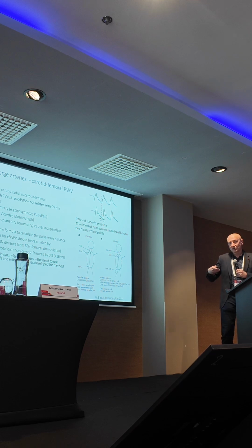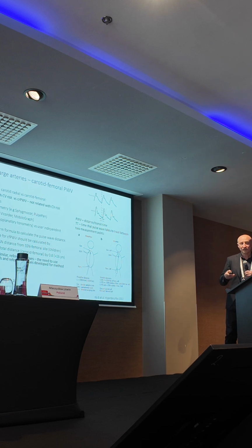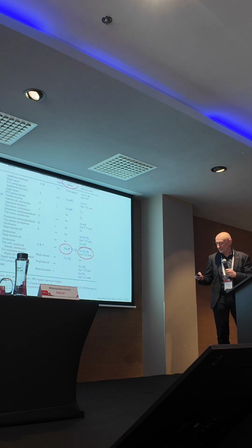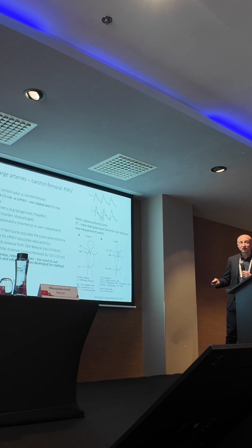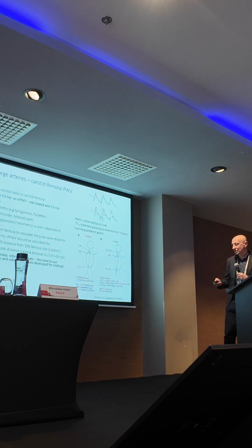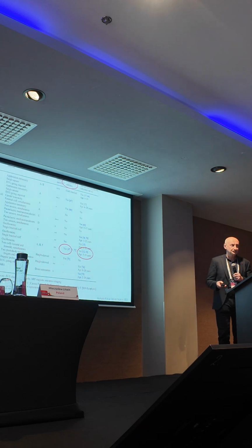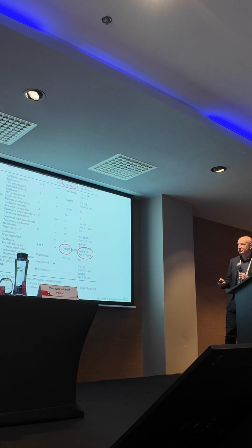The second important point is that, as I mentioned, there are different devices used to assess pulse wave velocity. So if you have any value obtained by measurement, you should refer it to a referential value. And those referential values are different for different devices, different for oscillometric devices and for applanation tonometry. So it is important to know if such a method is validated. And we have a table where the most often used devices are listed, and as you see, there is some information about validation in children.